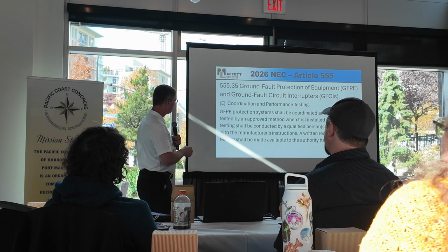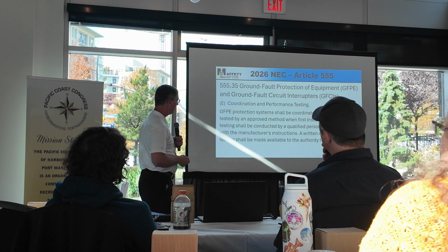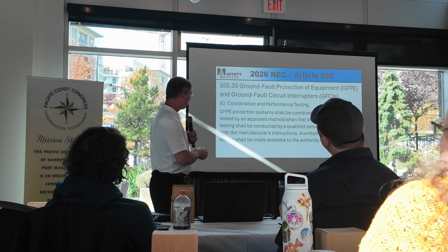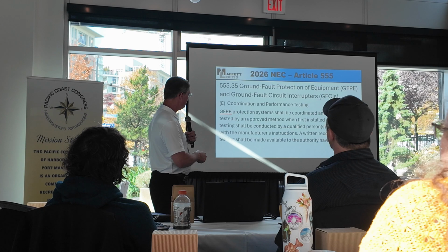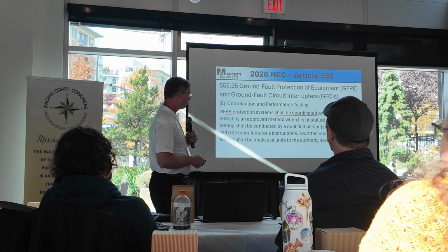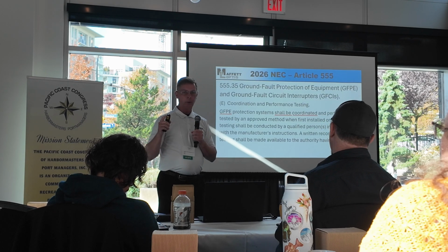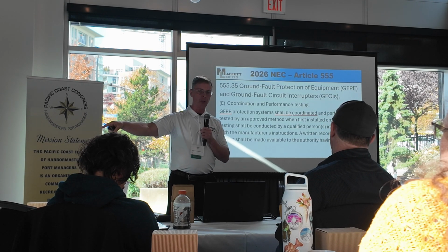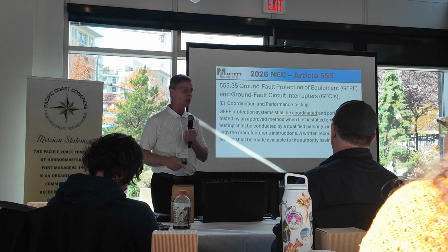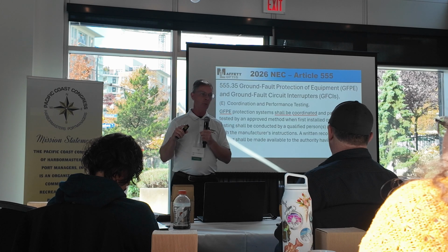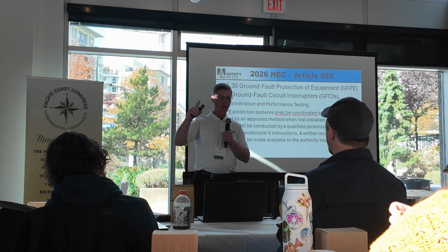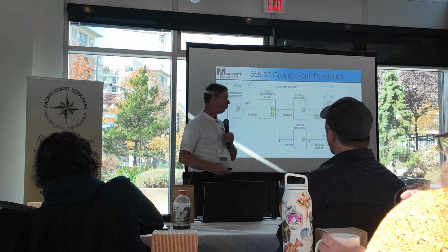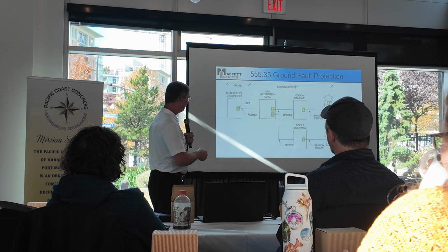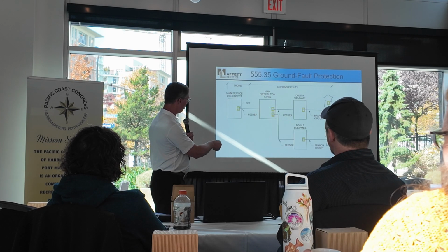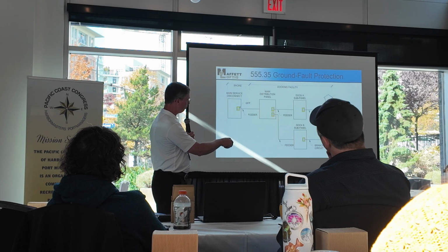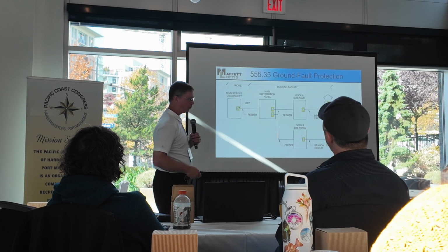And then under the same 555.35(E), this is a big one here, that coordination and performance testing is going to be required. GFPE systems shall be coordinated, and what that means is that the upstream GFPE won't trip when a downstream one sees a leakage current event. This is a big deal because I'm going in and repairing a lot of marinas where the main trips, when you've got the main 100 milliamp will trip, but the 30 milliamp won't. And I'm going to show you this just real quickly. So you've got the shore service. This right here is the disconnect on the shore. Then you've got on the docking facility a main distribution, say dock A with multiple shore power on it, and then dock B with multiple pedestals with shore power.